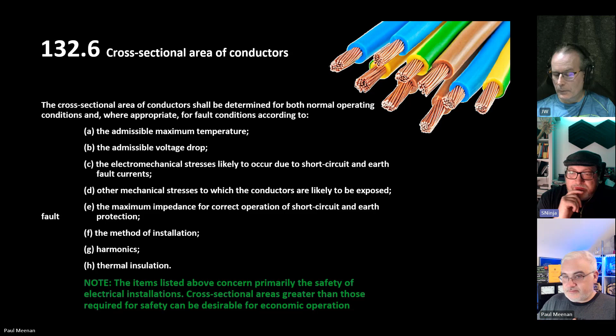So folks, if you've got a means to set up a copper manufacturing company, watch the money roll in. Let's add the caveat though, that just adding a bigger cable size will mean you have to redo calculations, because you'll have higher fault currents and higher thermal constraint challenges. So there's always a knock-on effect to it. But fun - yeah, it's an interesting one.